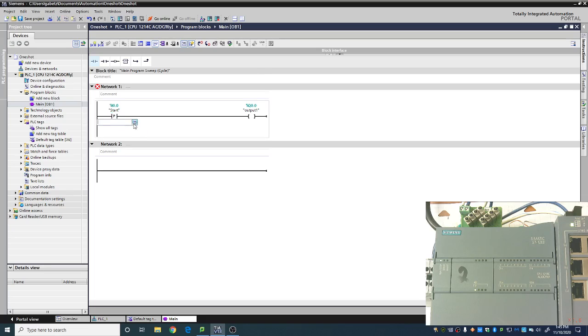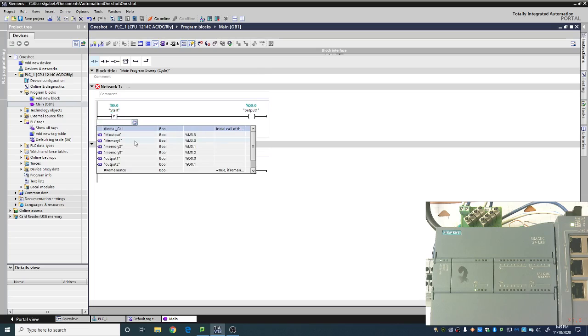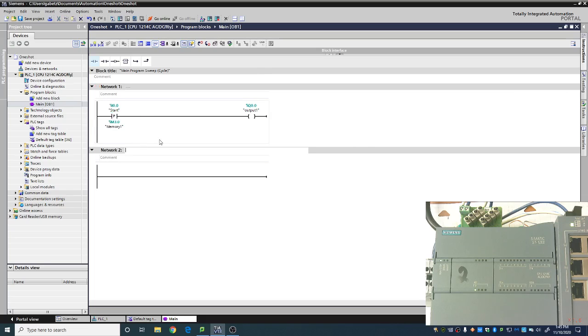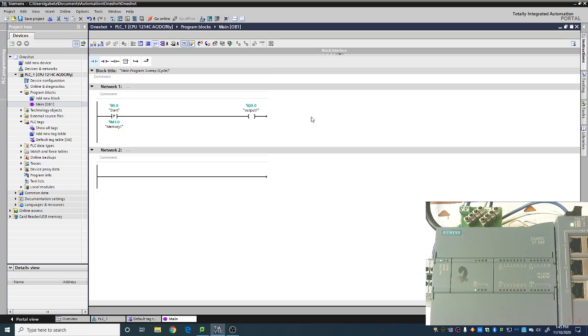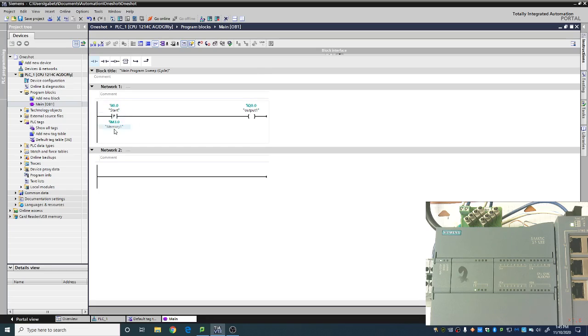This is what I like to call the one-shot's memory. If it doesn't know what happened the last time around, what the state of that input was the last loop of the code, it has no way to know whether there is a transition. So we need to have some place to store the previous loop's state of that input. That's what that bottom is. So on an input one-shot, we have our actual input that we're checking for that transition for, and on the bottom we have the place to store the last loop of code's state for that specific input.